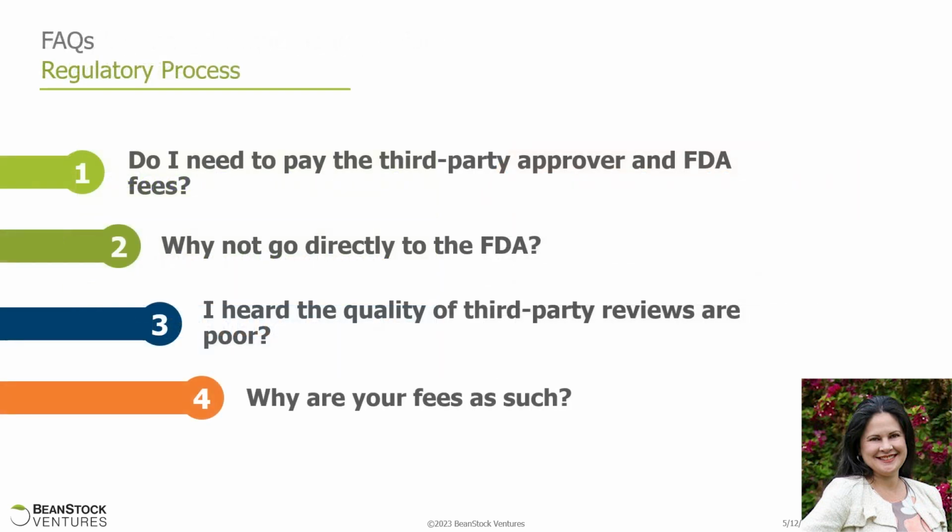Here's a list of common questions we get asked. One of the top questions is, do I need to pay the third-party approver and the FDA fee? No. You pay the third-party approver directly based on their payment terms. As I mentioned, there's no real fixed fee. Each third-party review organization is free to charge what they think is appropriate for their services, and you don't have to pay the FDA. So you're going directly to the third party, paying the third party, and interacting with the third party.